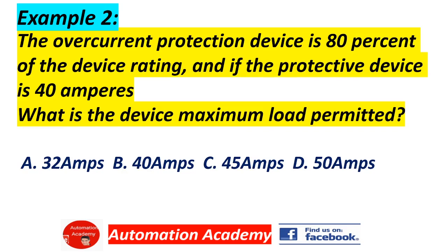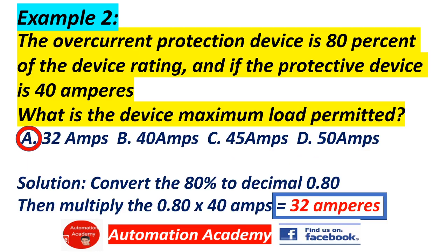Example number 2: The overcurrent protection device is 80% of the device rating, and if the protective device is 40 amperes, what is the device maximum load permitted? Answer: A, 32 amps. Solution: convert 80% to decimal, 0.80, then multiply 0.80 by 40 amps. The answer is 32 amps.